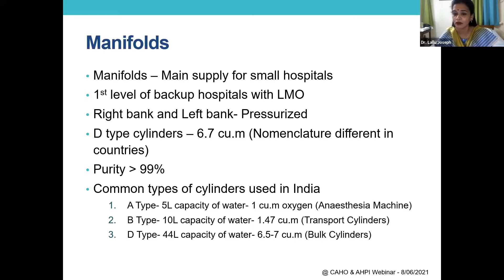Common types of cylinders used in India: the A type, which is about 5 liter capacity of water. That's 1 cubic meter of oxygen, which is what we use in our Boyle's apparatus, the very small cylinders. The B type is what we use for transport. That's 10 liter capacity of water, 1.47 cubic meter. And the D type is what we use in the manifold, that is 44 liters capacity of water, and that's about 6.5 to 7 cubic meter of oxygen. So those are the bulk cylinders.